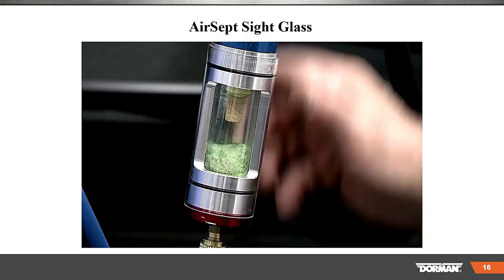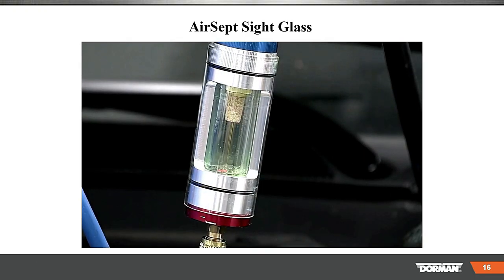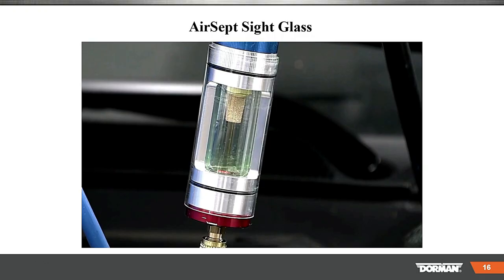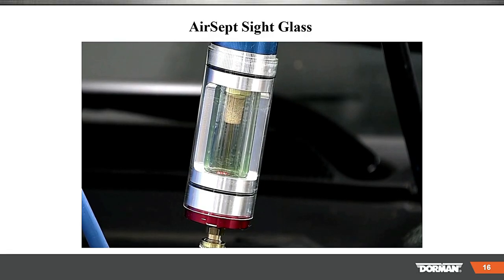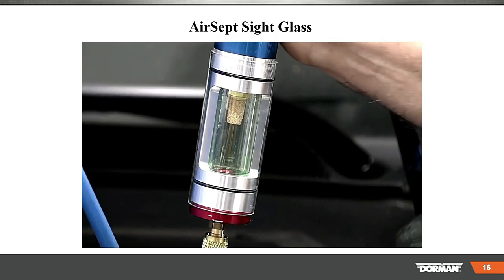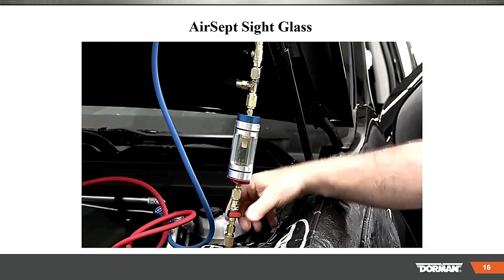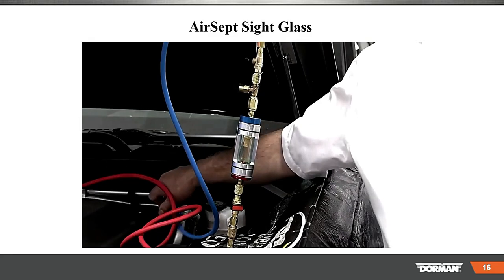As it's boiling, the bubbles, that is telling us the suction side of the compressor is actually pulling this in, and open that very slowly, okay? Now we let it go all the way, I'm going to open it up till there's nothing in there. And now that you're clear, we are going to shut the valve, both valves shut, and we could then shut the low and high side here.